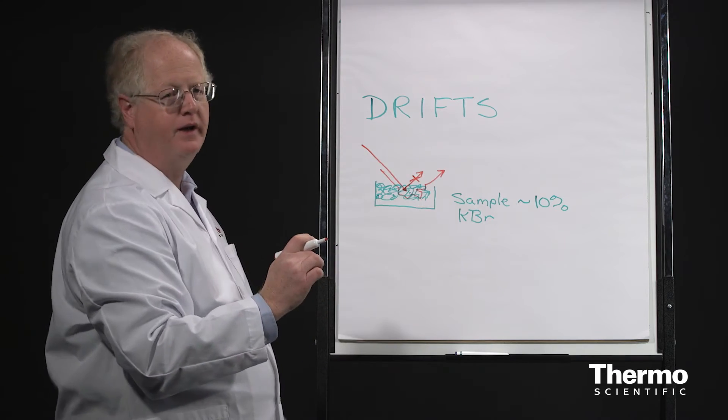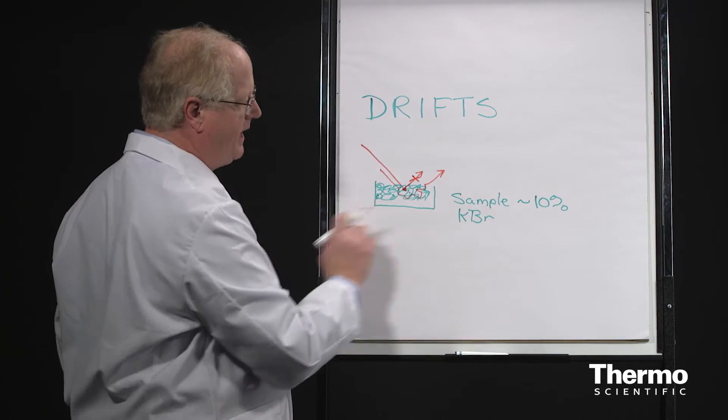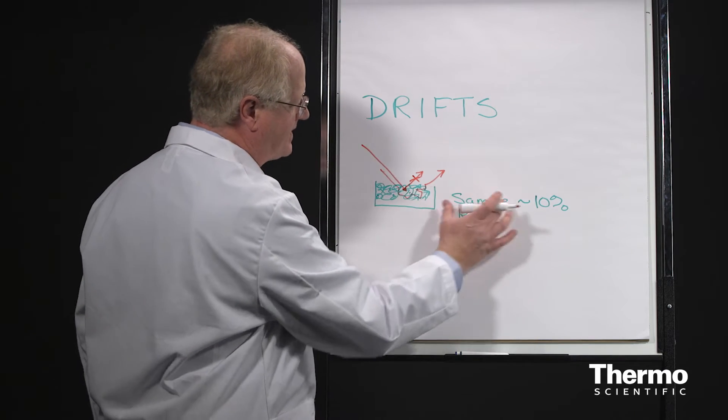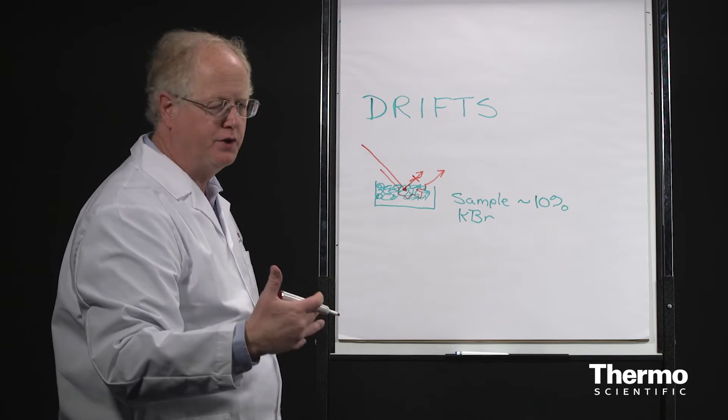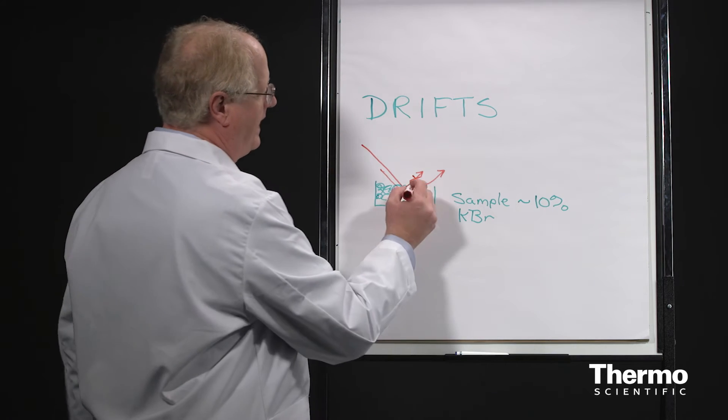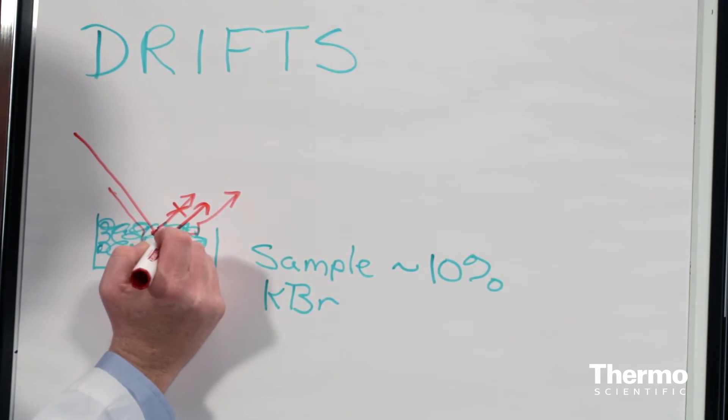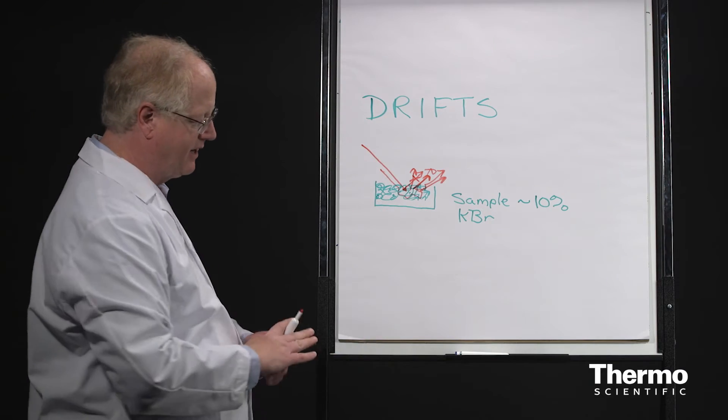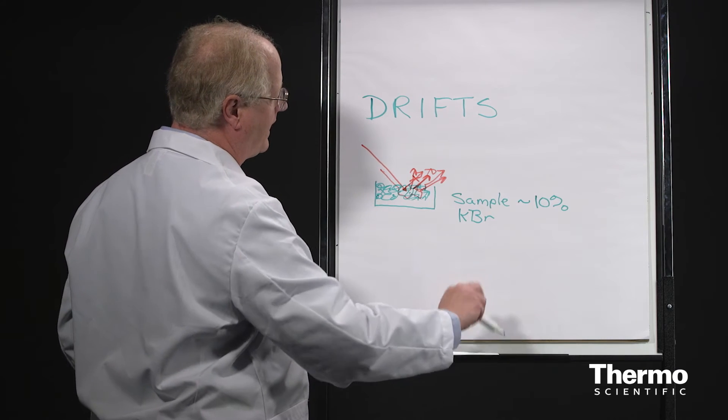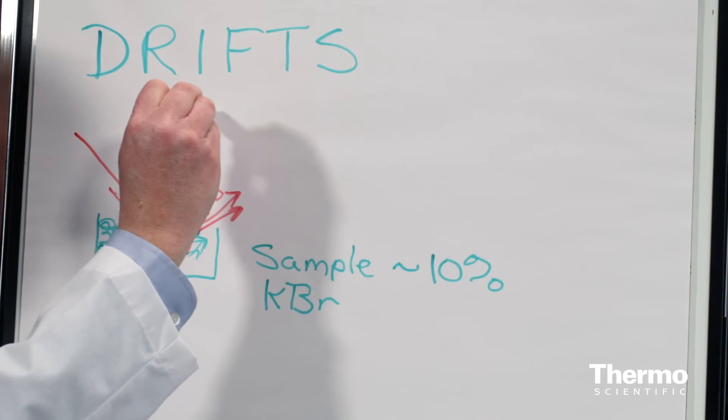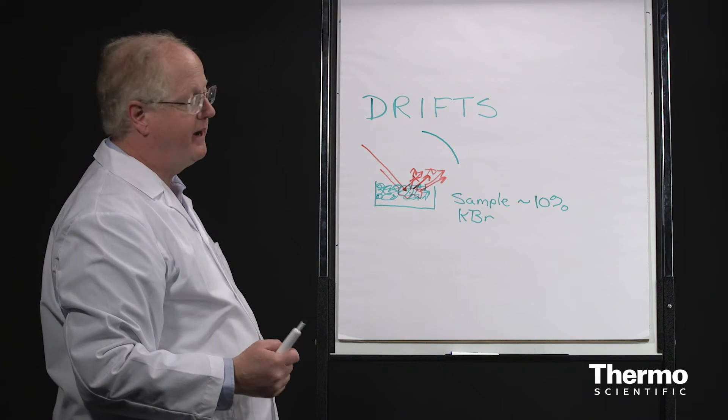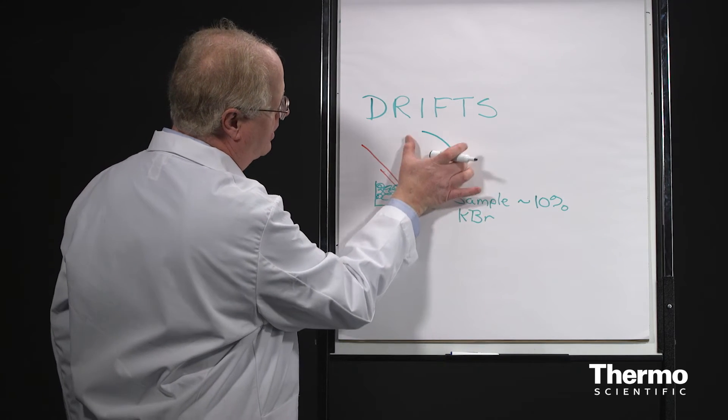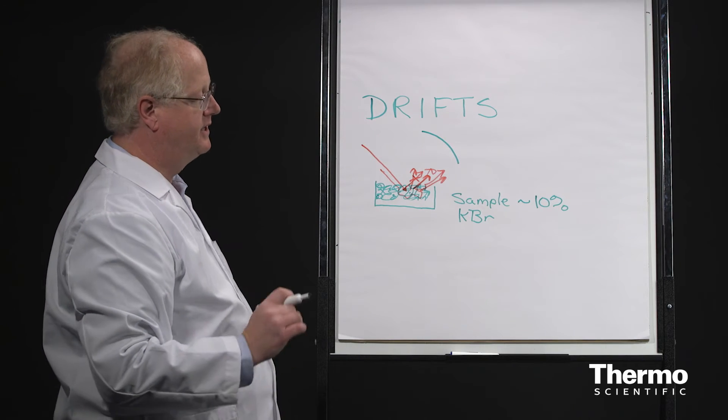And while it's bouncing around, it's hitting these particles of KBr and occasionally passing through a particle of the sample. And as it's doing that, it's storing up, so to speak, the absorbance of the sample. And then that diffusely reflected light, which comes back out, is actually carrying the signal. And it's this diffuse light, which is then gathered by a mirror, what we call a compound parabolic collector or a CPC. That mirror collects that light and directs it onto the detector.